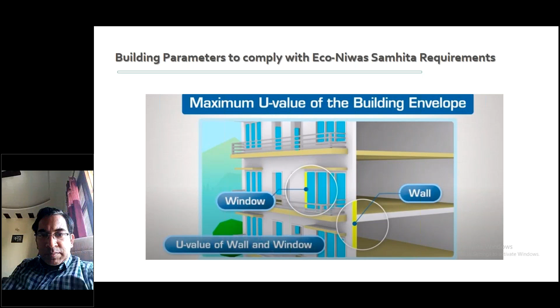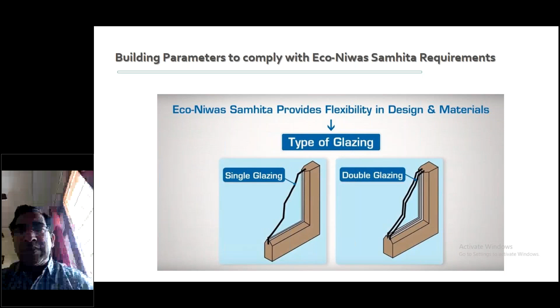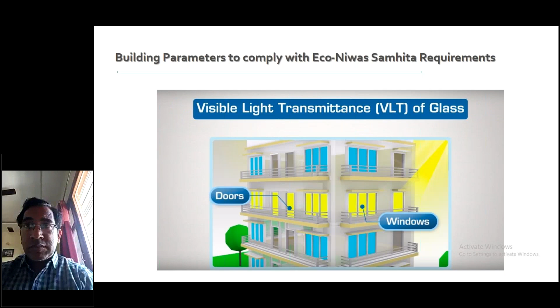There is no specific requirement mentioned by ECBC. ECBC only talks about the SHGC, the solar heat gain coefficient of the glass, and the VLT part. Your building glass should be such that your SHGC meets the requirement defined in ECBC, and the VLT of your windows, the visible light transmittance, should be such that you can capture the natural daylight available in the environment. You can capture daylight as much as possible through the glass property, which is VLT, visible light transmittance, so it should be as high as possible.